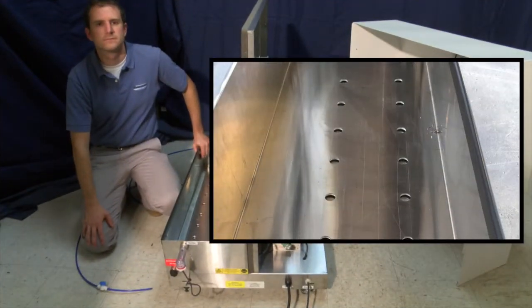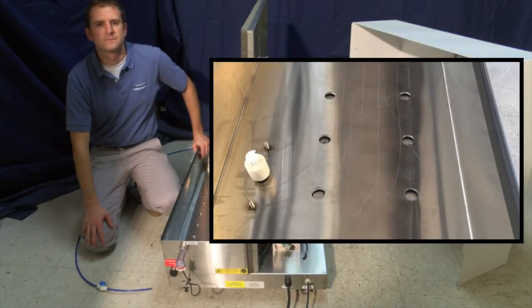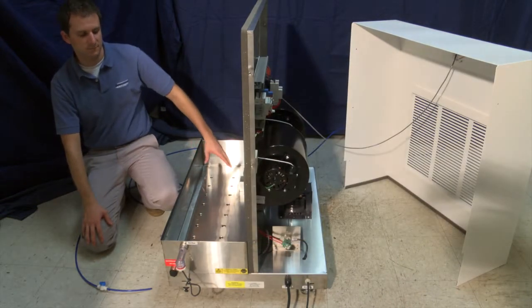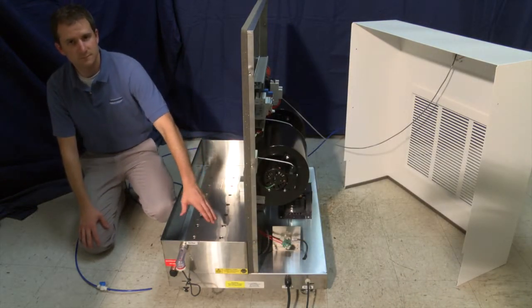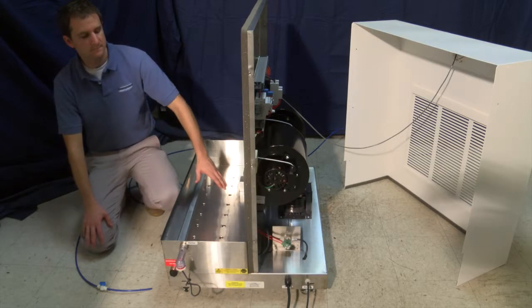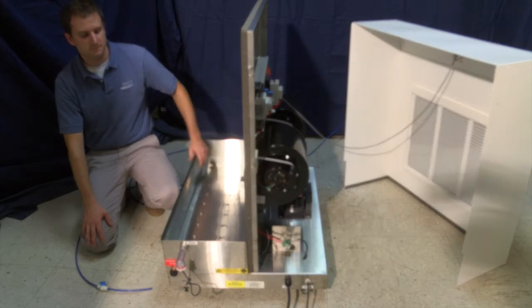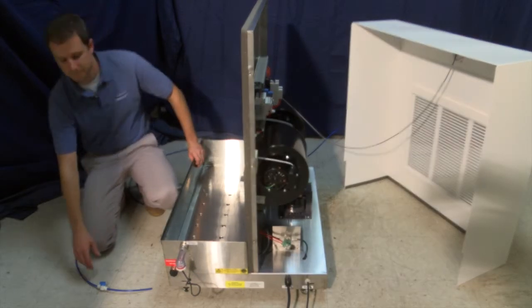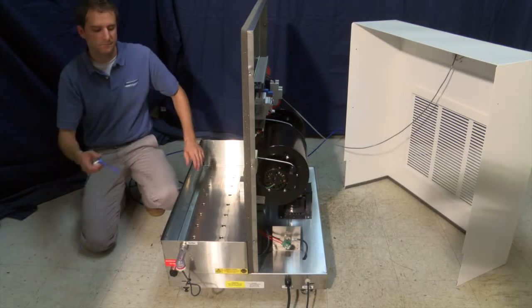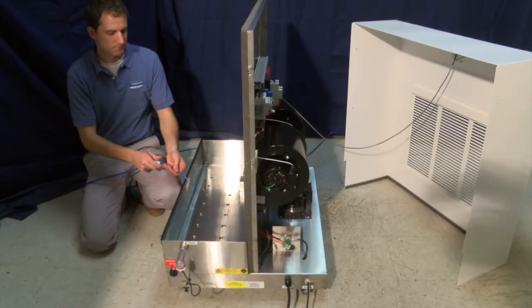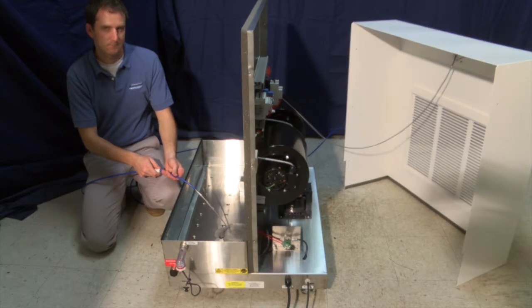Let's take a closer look at the transducers now. You can now see the water pan and transducers. First, make sure the water pan is clean and clear of any debris from construction or unpackaging. Next, you're going to want to prime the transducers with a small amount of water. The transducers can never operate dry, so covering them with about an inch of water is a best practice.